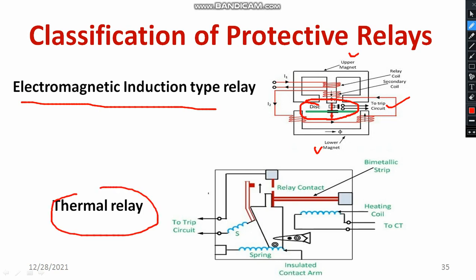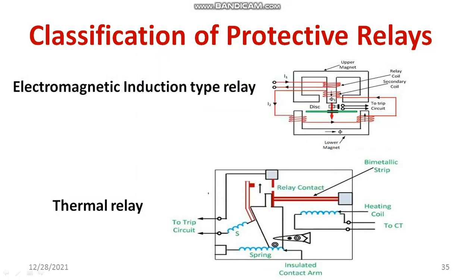Regarding the thermal relay in more detail: there is a heating coil connected to the current transformer. A bimetallic strip is activated based on the heating effect. If the temperature is very high, the relay contact gets activated, thereby connecting to the trip circuit. The current transformer is used for measuring purposes. Based on excess temperature — whenever current or voltage is passed into the coil — the temperature of the metal part increases and that is connected to the tripping circuit. This is how the thermal relay operates.